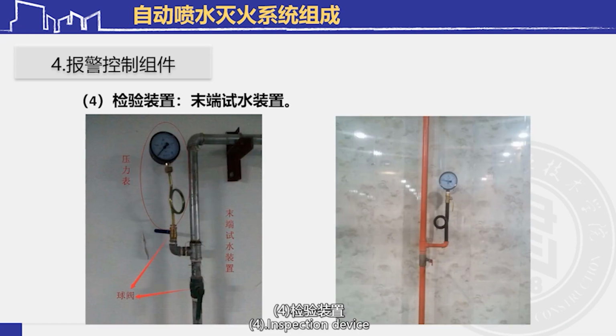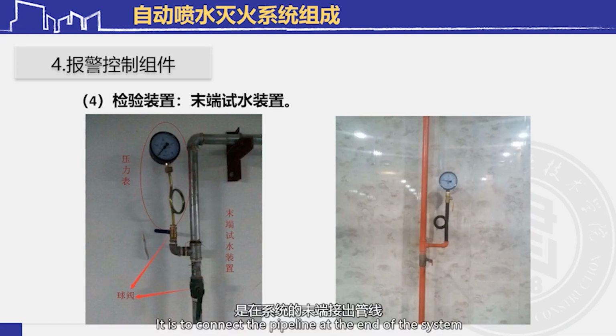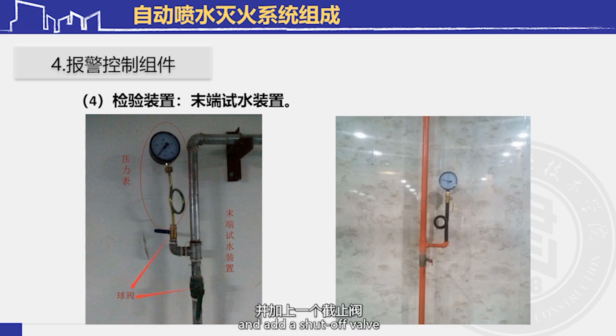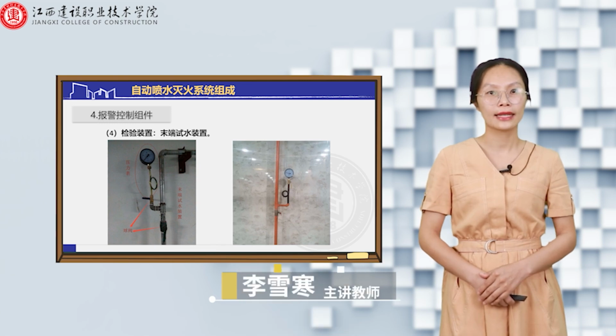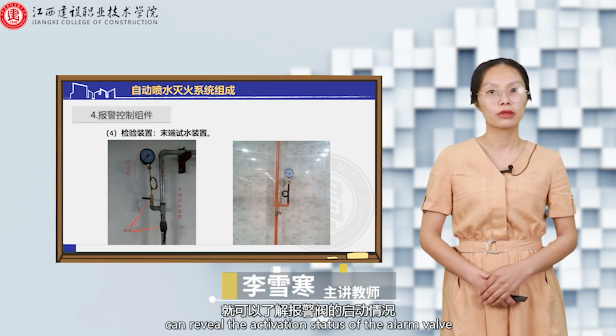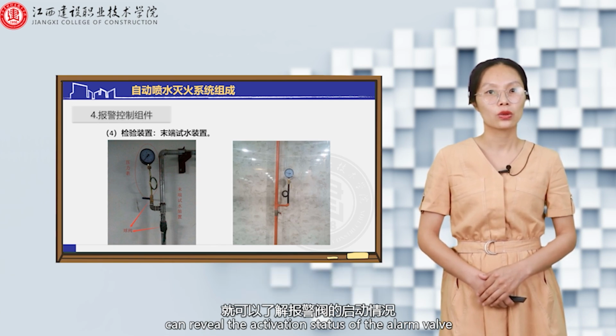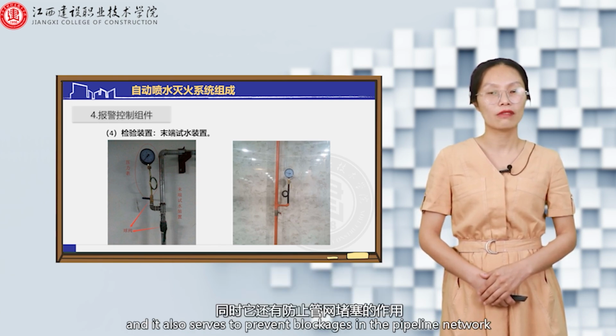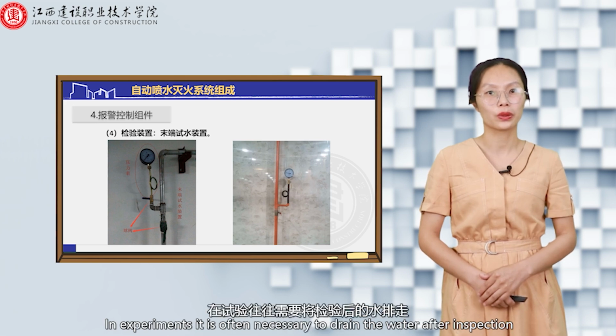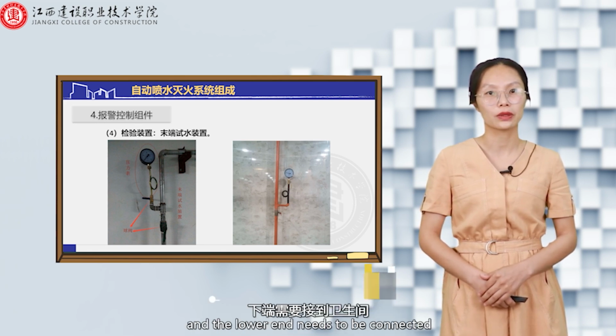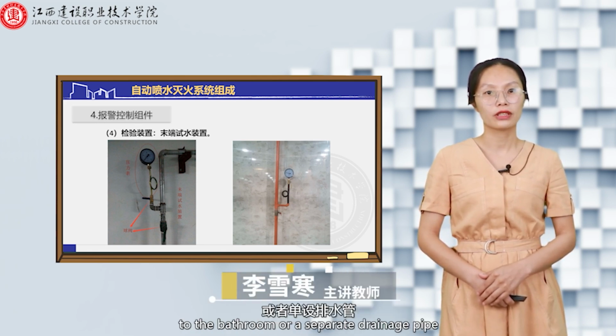Fourth, inspection device. It is to connect the pipeline at the end of the system and add a shut-off valve. Installing a pressure gauge in front of the valve can form an inspection device. During inspection, opening the shut-off valve can reveal the activation status of the alarm valve, and it also serves to prevent blockages in the pipeline network. In experiments, it is often necessary to drain the water after inspection, and the lower end needs to be connected to the bathroom or a separate drainage pipe.